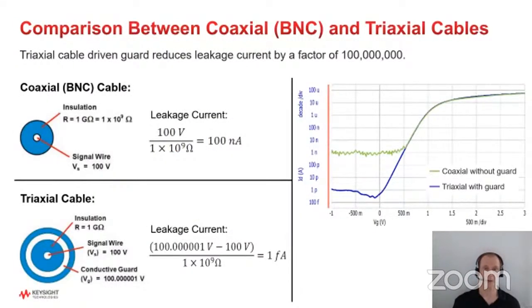This slide shows one example of how to think about the reason we use triaxial cables. At the top, if we had 100 volts going through a BNC cable, even with a gigaohm of resistance in the insulator going to the outer ground shield, that's still a significant amount of current that can leak out, about 100 nanoamps. So if you're trying to measure very low levels of current, you obviously can't do that with a standard BNC cable. Whereas on the bottom, because the driven guard is kept at a potential very close to what we're actually driving, within maybe 1 part in a million, you get extremely low leakage from the triaxial cables. On the right, you can see an example graph of the difference between using a coaxial and a triaxial with a driven guard.